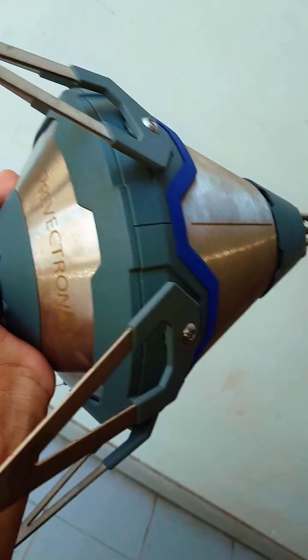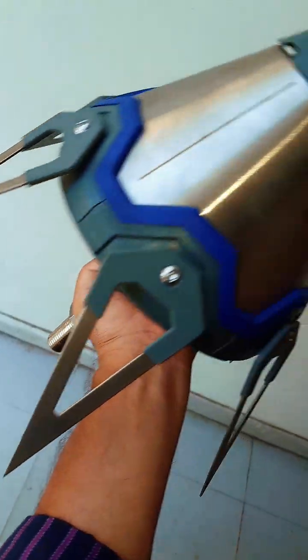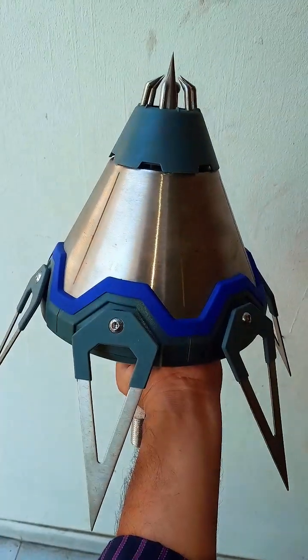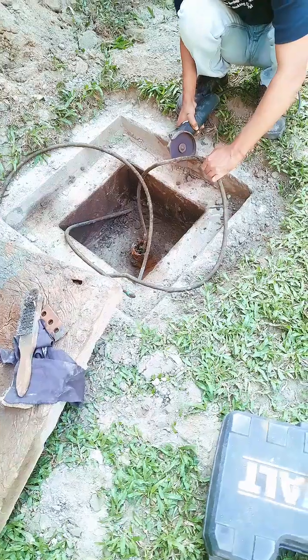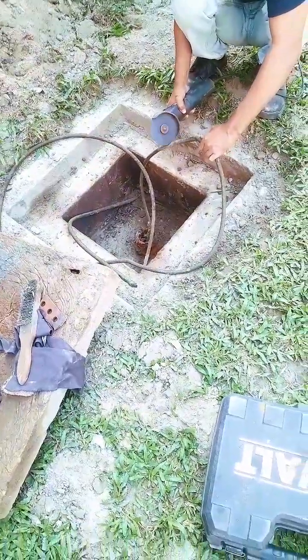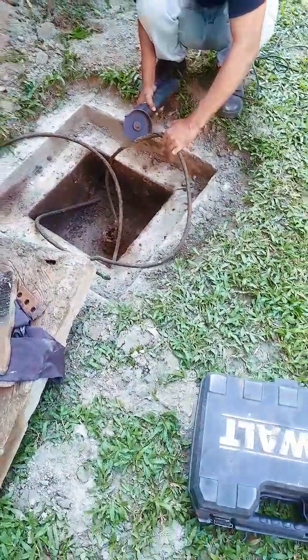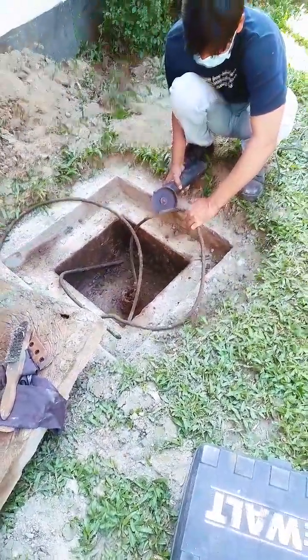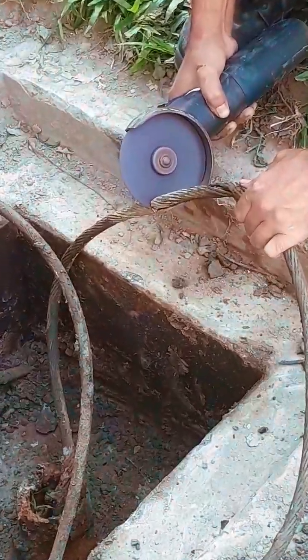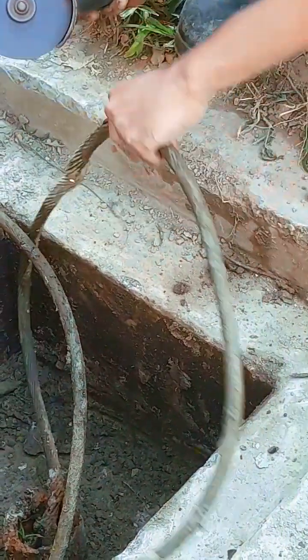The condition we found. This earthing pit is a boring type, 120 feet deep. The main grounding conductor is a 95 Rm copper round conductor. Because the pit remained buried under soil and sand for many years, corrosion developed on the cable surface. The conductor was still connected, but physically it was unsafe.